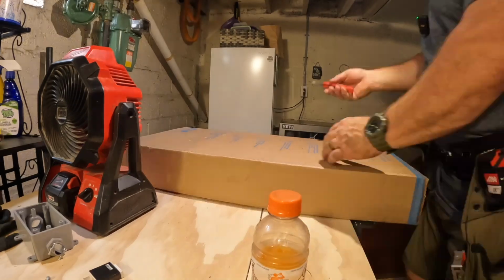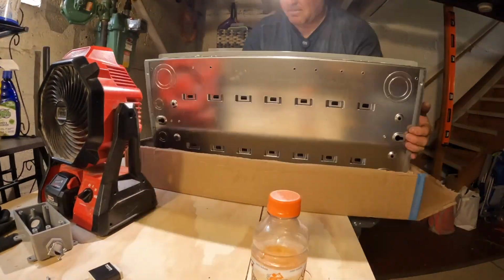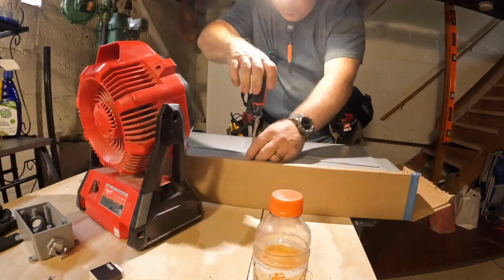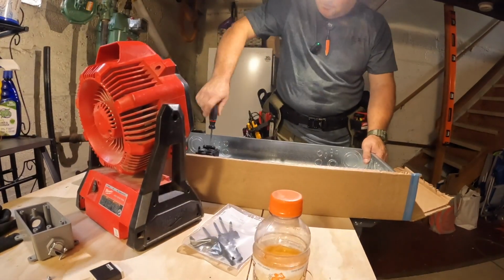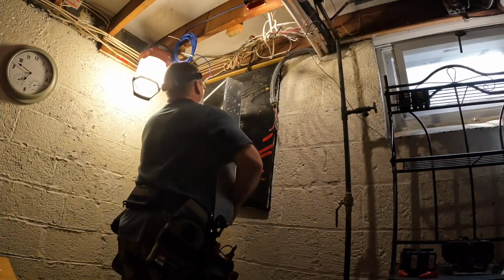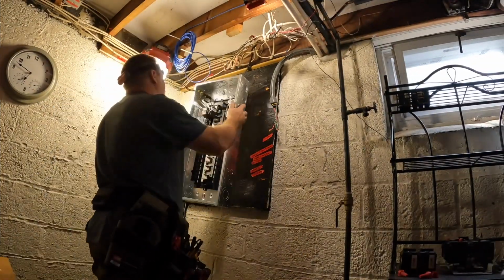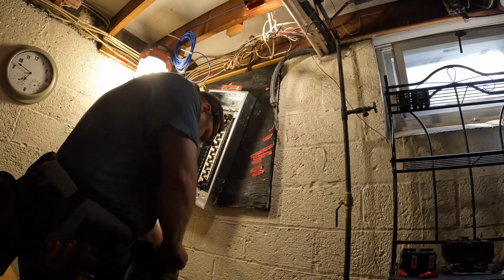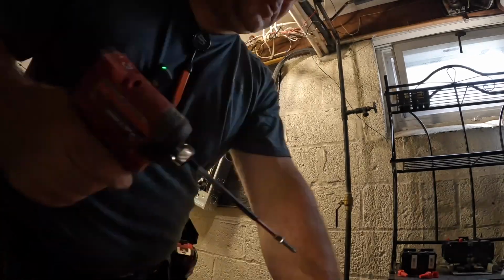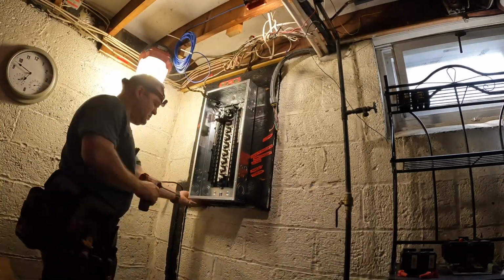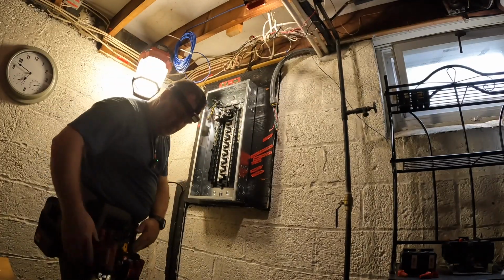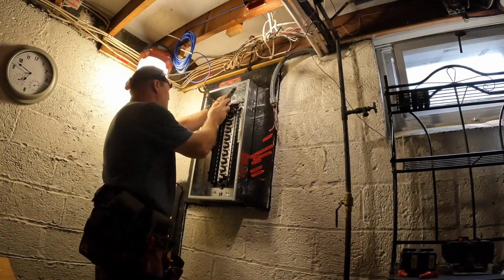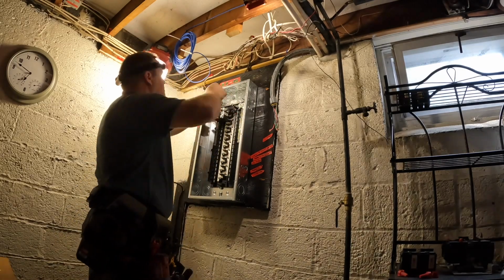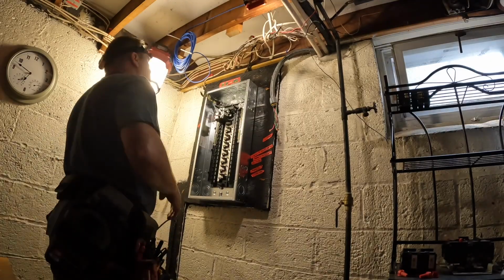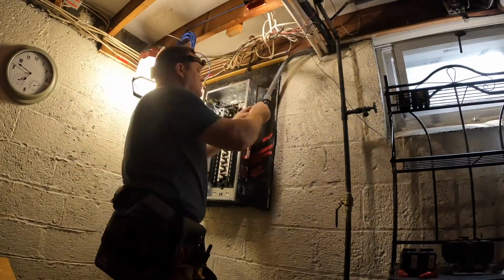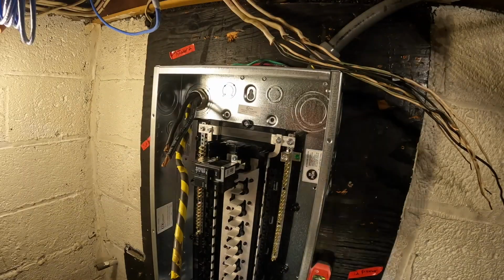So once we remove all the branch circuits, we remove the old panel and disconnect the lock nut and the bonding bushing, and now I'm able to open up my new panel and install the new panel. Now, one of the challenges here is I wasn't sure how this panel was going to sit on this old mounting board. The mounting board that's there now is on so good that I didn't feel the need to actually have to change it. Tyler, the customer, was okay with this, and so the biggest challenge there is this panel going to overlap the mounting board, and it didn't. As you can see, it goes right to the bottom there, and we used a concentric knockout that was existing. That was a concentric knockout on the electrical panel itself, so I didn't have to make a custom knockout for this, which always makes for an easier installation.